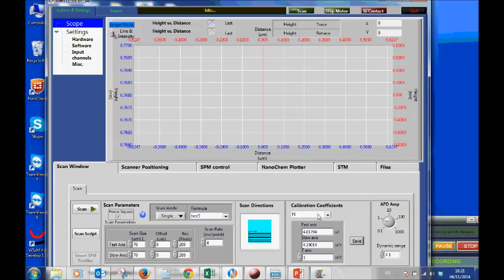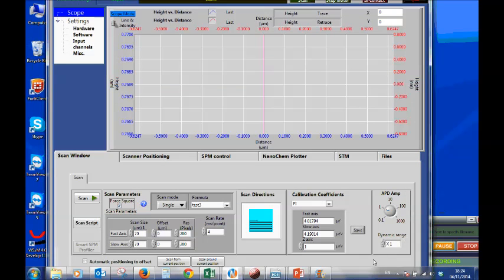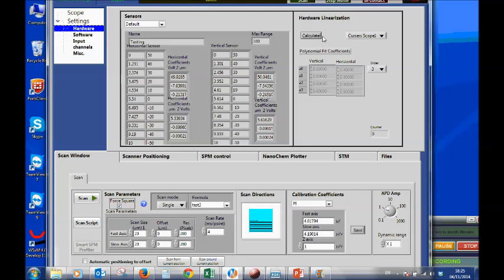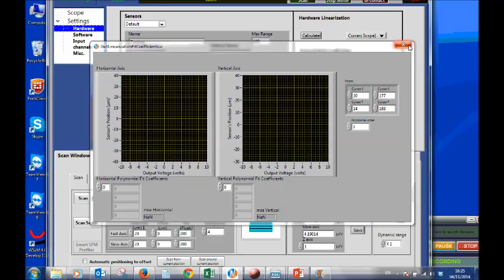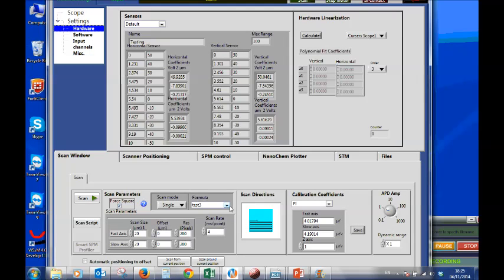Then first we're going to scan in the air. Now let's say that we want to scan, using the sensors later on, an area of about 20 by 20 micron. So first we're going to choose here 20 by 20, and we can scan in the air using first the formula for the calibration. We say there's a calibration file. So because we're scanning in the air, we can scan a bit faster. So the resolution should be about 200 pixels, and we can scan about with 4 milliseconds per point. And after we're done scanning, we go to hardware and we press calculate. Here you will see lines. Then we're done with the calibration, and we can choose sensors and scan using the sensors.